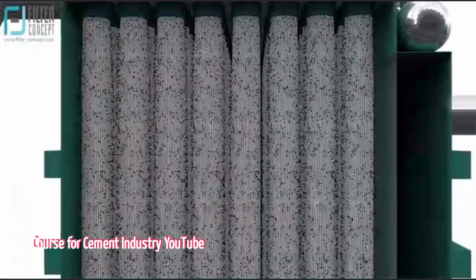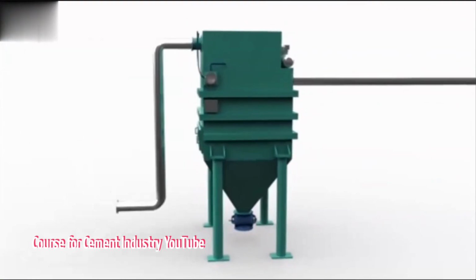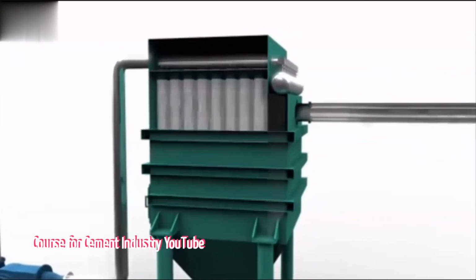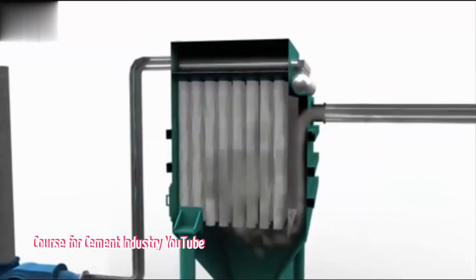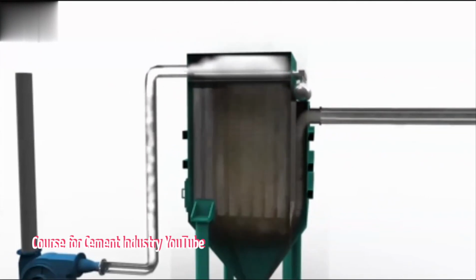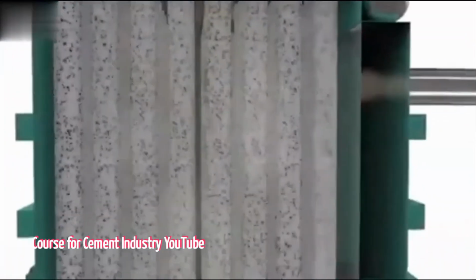It really is. And maybe a final thought to leave you with. Think about the fabric itself. The engineers have this constant tightrope walk. How so? Well, you want a fabric that's incredibly efficient at capturing tiny particles, which usually means a very tight weave or dense felt. But the tighter it is, the faster the pressure drop builds up, meaning you need to pulse clean it more often. And more cleaning means more wear and tear on those expensive bags. Precisely. So they have to find that perfect balance. Effective filtration versus bag longevity versus cleaning frequency. That trade-off, hidden in the material science, is really the silent engineering challenge behind keeping industrial air clean day in, day out.